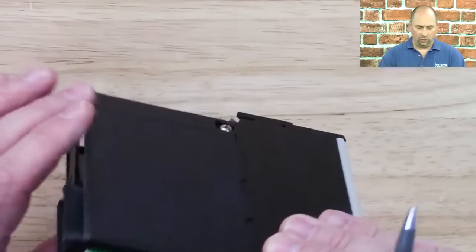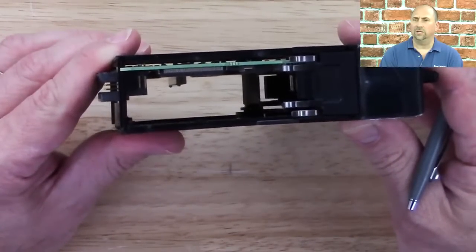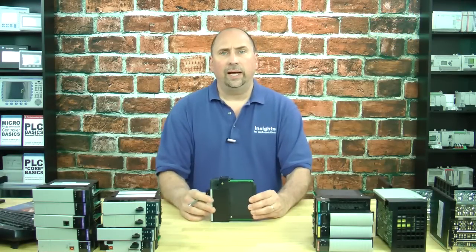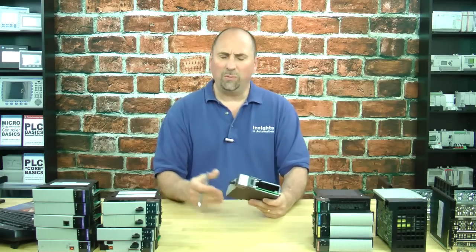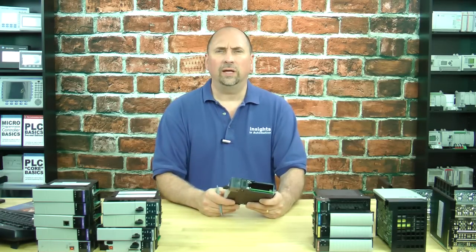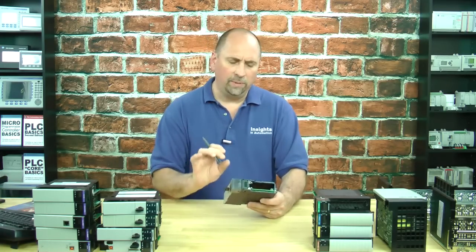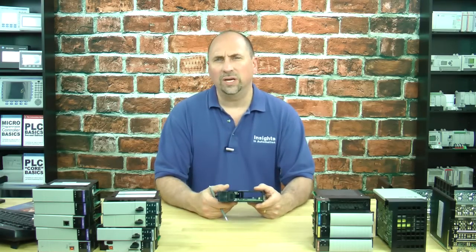Something else I want to show you is if you look inside, you can see a connector in there. I know it's hard to see, but that connector is where you would plug in additional memory. So the L1 had the capability to be upgraded. You could buy it as a base model with 160K — Rockwell said that was like the equivalent of a SLC 5/03 as far as comparable memory. You could also buy it with either a meg or two of memory. There were actually four memory sizes, going up to two megs of memory.